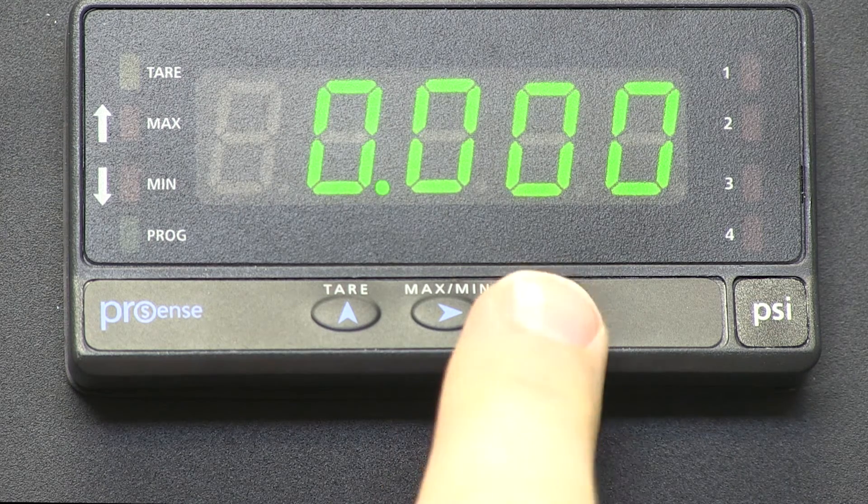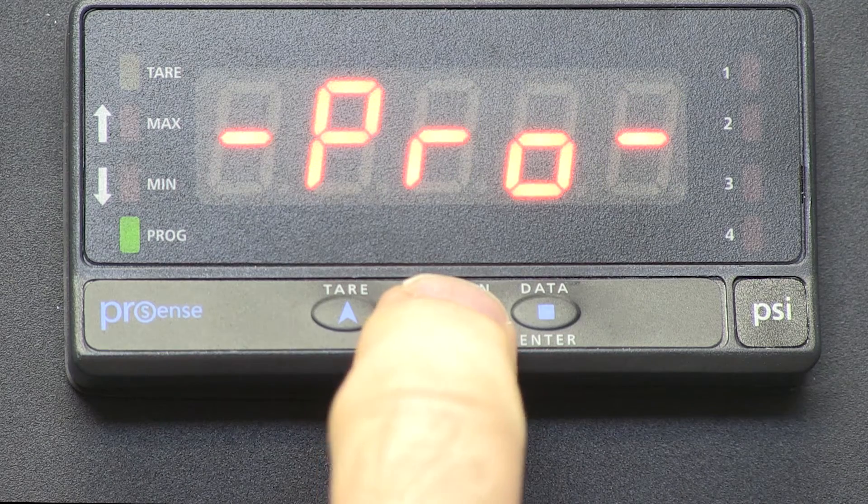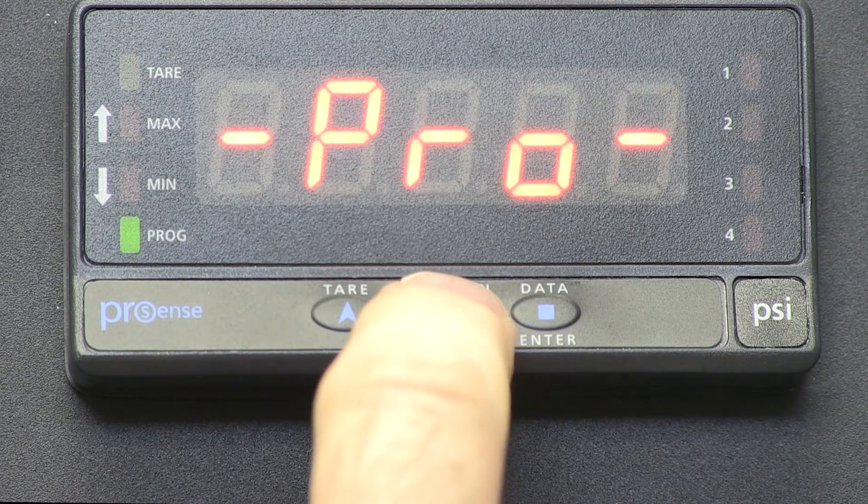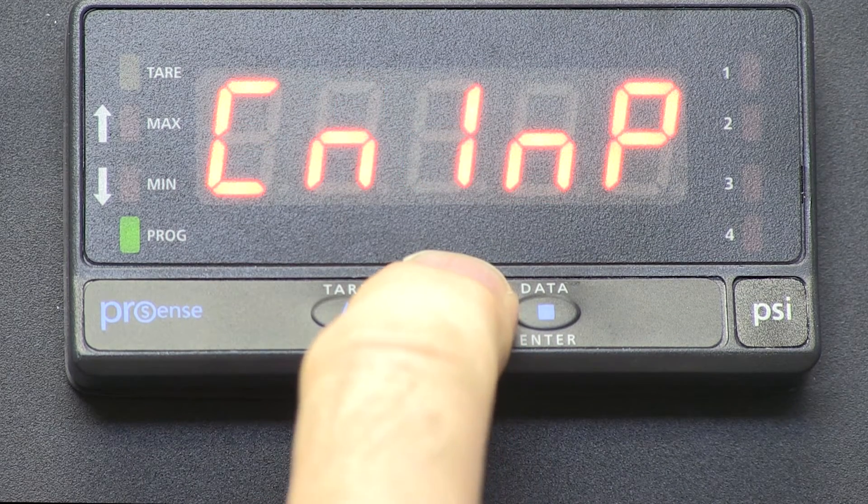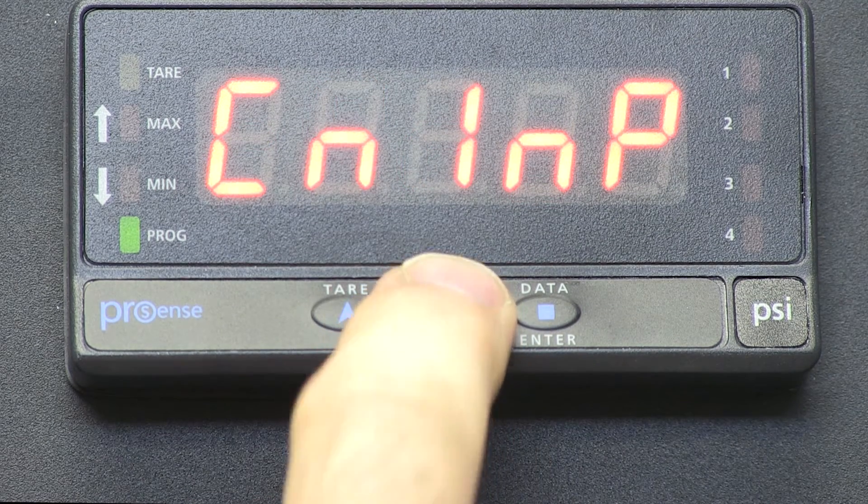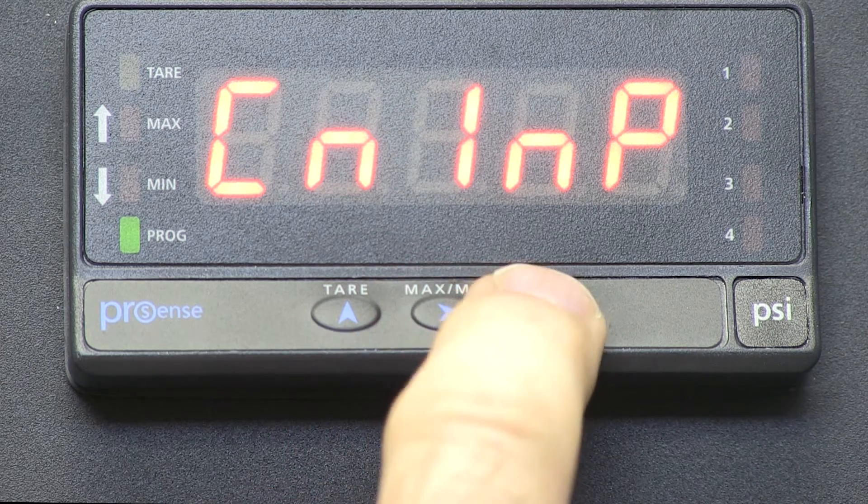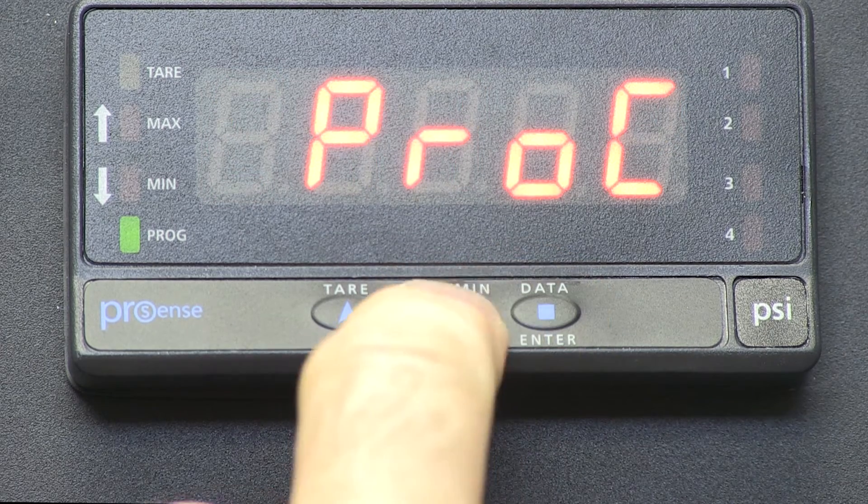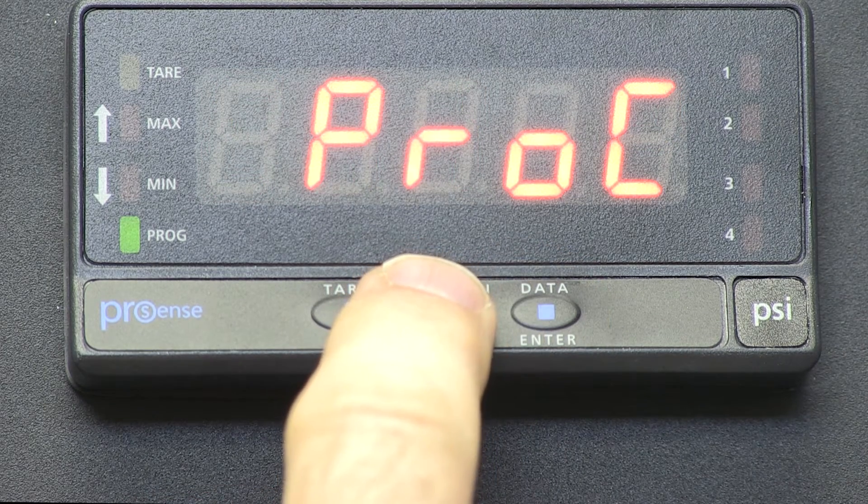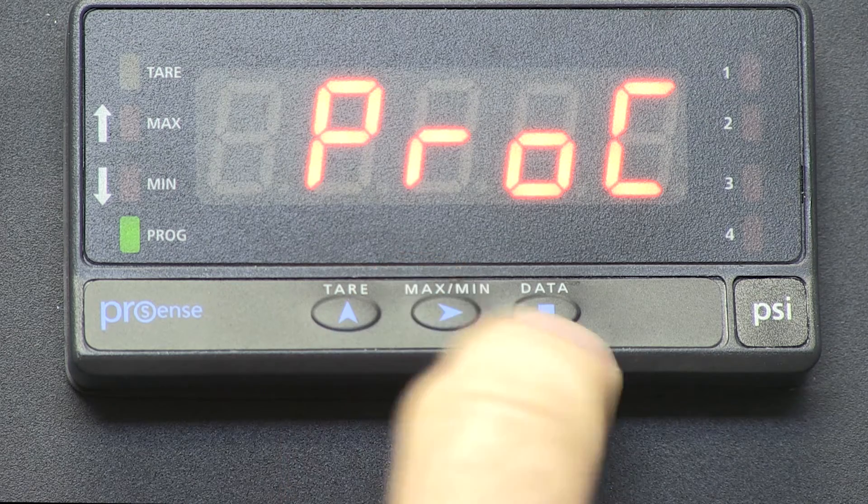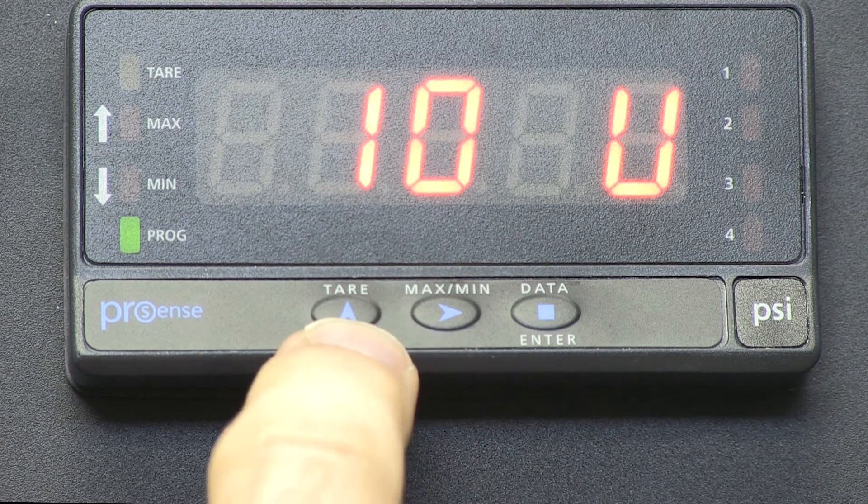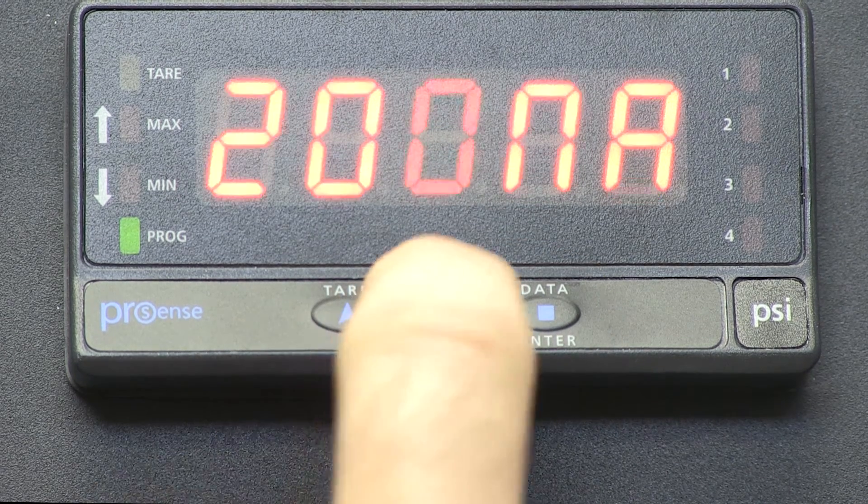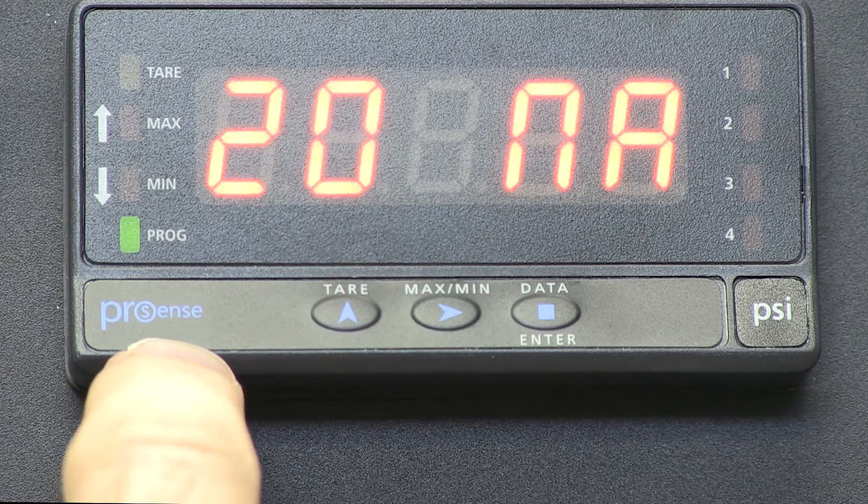First we will go to ENTER, PROGRAM, we are going to go to CONTROL INPUT, and we want to do PROCESS, and we want to enter PROCESS CONTROL, and it gives me the options of 10V or 20mA. We select milliamps.